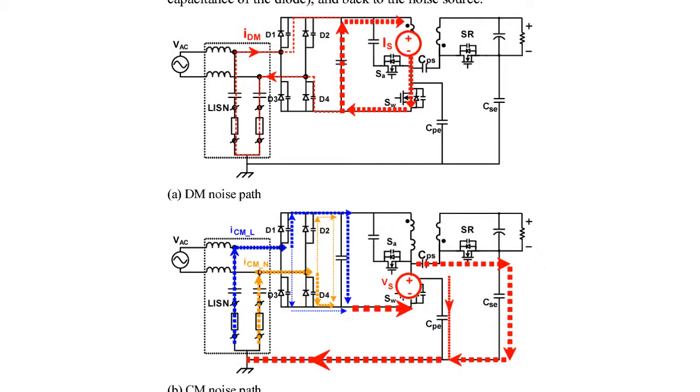Common mode noise impulses tend to be higher in frequency than the associated normal mode noise signal. This is expected since the majority of common mode signals originate from capacitively coupled normal mode signals. The higher the frequency, the greater the coupling among the conductors: line, neutral, and ground.